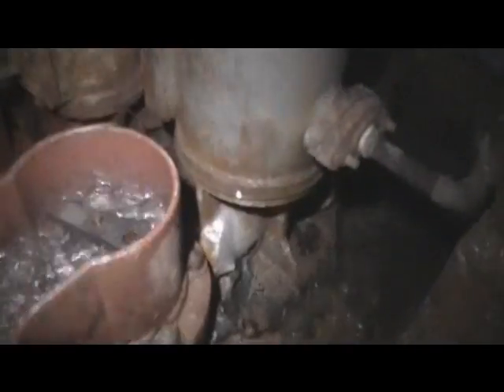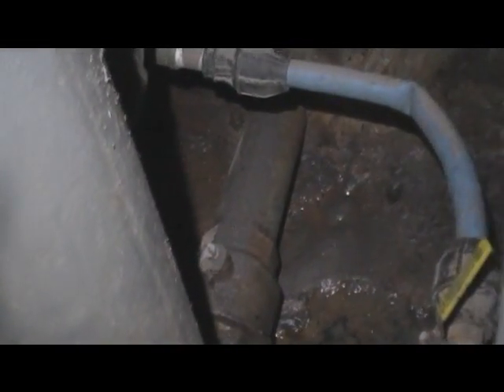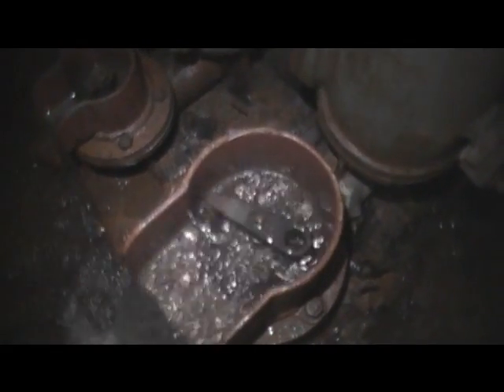There you go - Green and Carter Limited. This is it. Vulcan Brooks, Winchester. And then you have a quote and contact details for contacting them. So there you go, this is where you would look. Have a look at that diagram I showed you earlier. Water coming in through that pipe there. Unfortunately the valve is leaking and broke. Anyway it comes in - in there is where the rubber valve is. It doesn't quite shut cleanly unfortunately, but it's still running. And then you have your pressure vessel here. There's a one-way valve in the bottom of it.